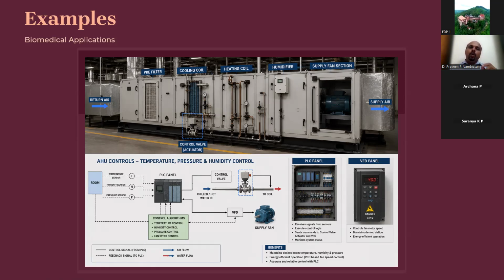Opening and closing of the cooling coil and heating coil supply will be controlled from the PLC panel, based on the sensor signal processing which comes from the room. The room has a sensor, and it goes directly into the processor, the PLC. The PLC will just check with the set point whether it is matching. If it is low, what has to be done? That signal will go to the actuator of the respective coils. So in this way, I can control the temperature of the room.